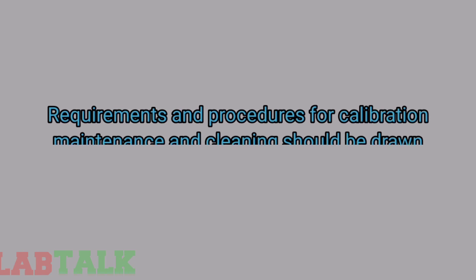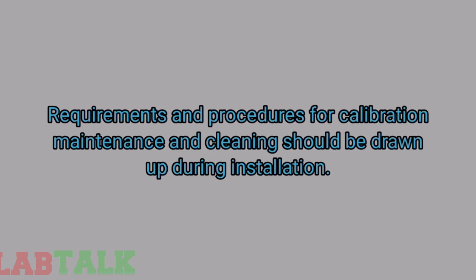Requirements and procedures for calibration, maintenance and cleaning should be drawn up during an installation, and documents regarding calibration, maintenance and cleaning should be prepared and their schedule should be fixed in collaboration or in discussion with the manufacturer. So, an ideal IQ report should include a validation protocol, installation qualifications, page numbers, title of the protocol, and name and address of the site of installation.